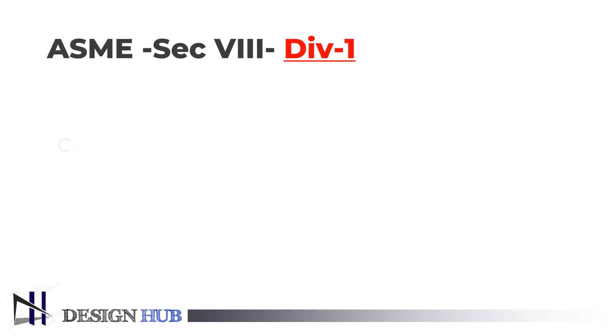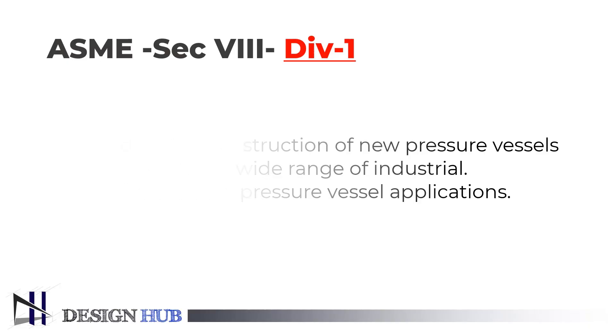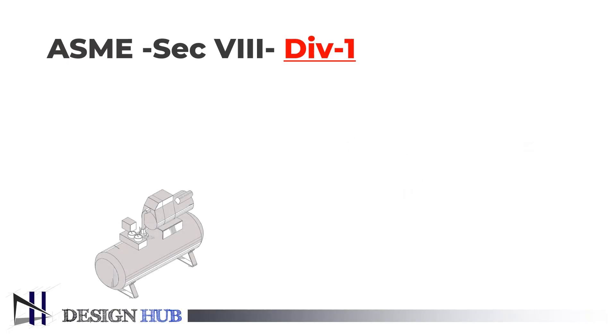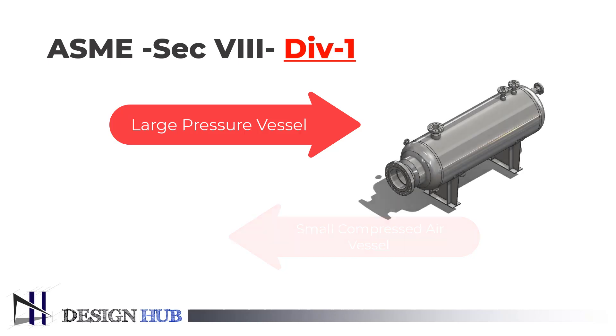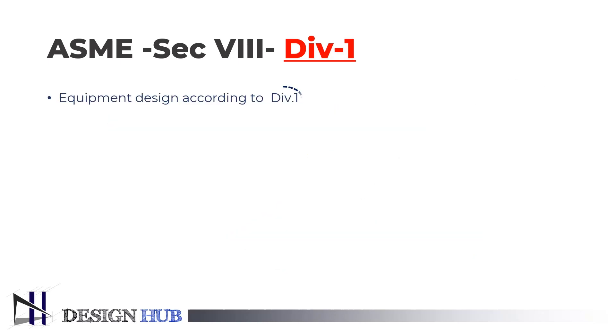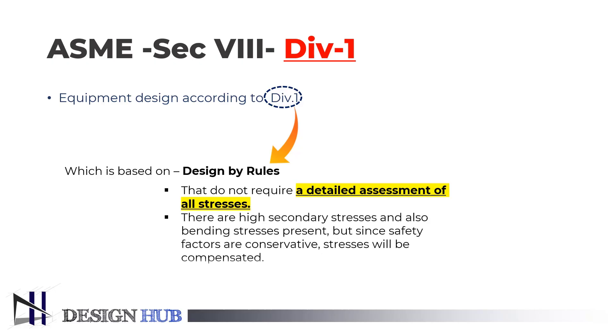ASME Section 8, Division 1, is created for the construction of new pressure vessels which cover a wide range of industrial and commercial pressure vessel applications. This applies to both small compressed air vessels and very large pressure vessels required by the petrochemical and refining industries. Types of equipment designed according to Division 1 do not require a detailed assessment of all the stresses, because of the compensation of stresses due to the conservative nature of safety factors.